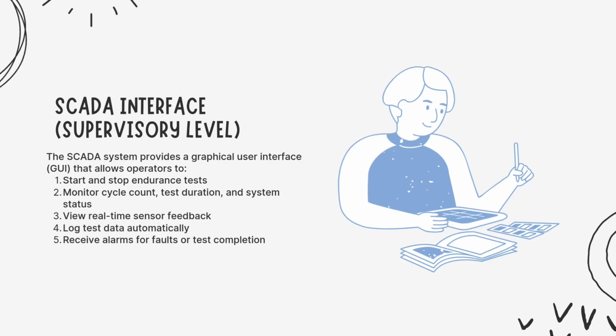For the SCADA interface, it provides a graphical user interface that allows the operator to start and stop endurance tests, monitor cycle count, test duration and system status, view real-time sensor feedback, log test data, and receive alarms for faults and test completion. Alright, that's all from me.